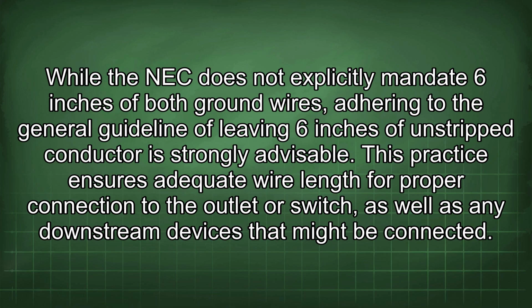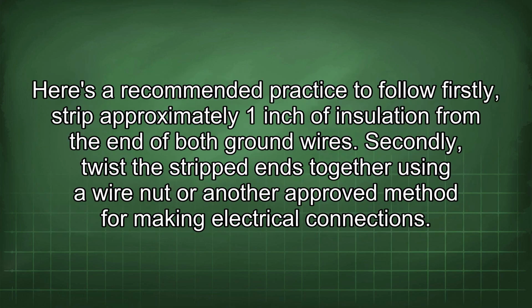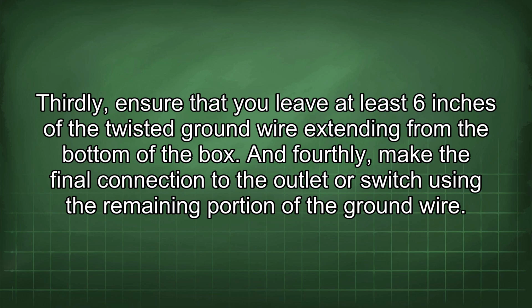This practice ensures adequate wire length for proper connection to the outlet or switch, as well as any downstream devices that might be connected. Here's a recommended practice to follow. Firstly, strip approximately 1 inch of insulation from the end of both ground wires. Secondly, twist the stripped ends together using a wire nut or another approved method for making electrical connections. Thirdly, ensure that you leave at least 6 inches of the twisted ground wire extending from the bottom of the box. And fourthly, make the final connection to the outlet or switch using the remaining portion of the ground wire.